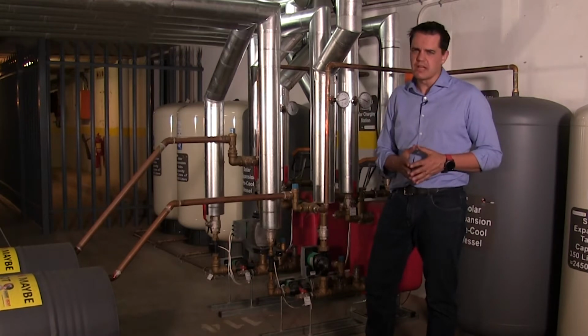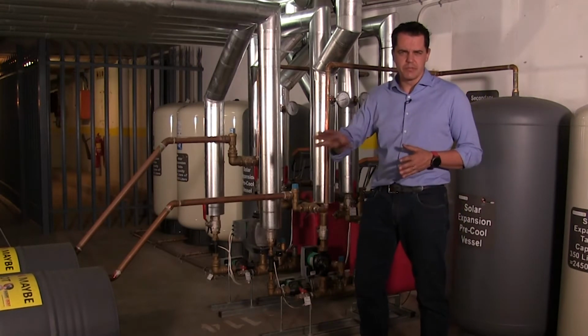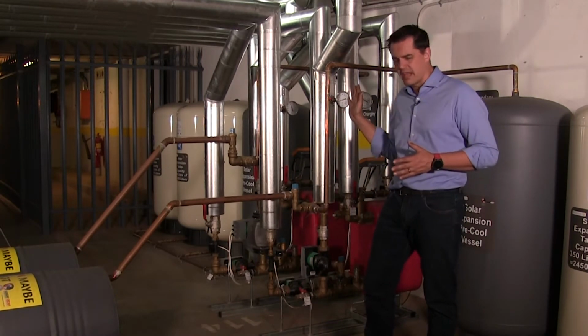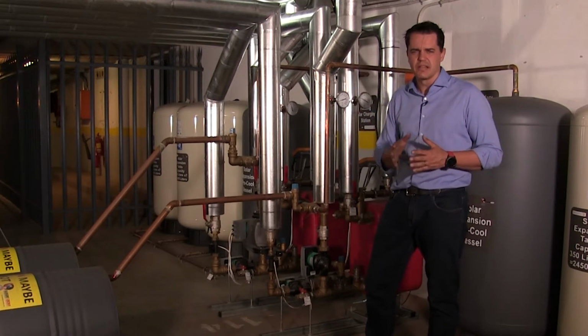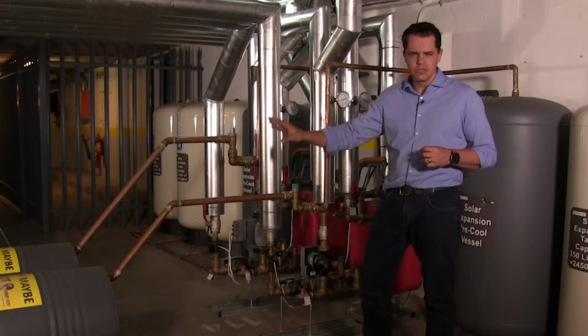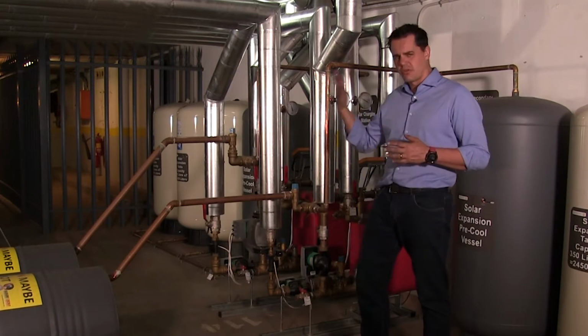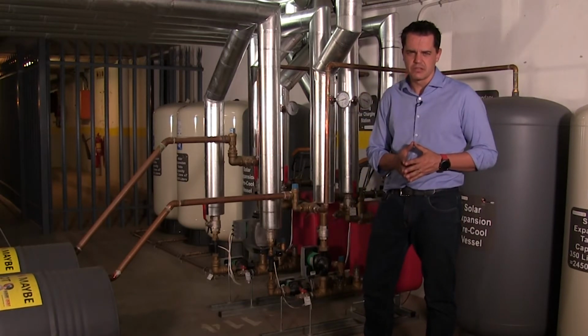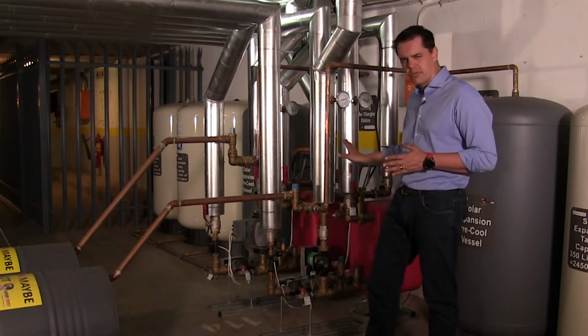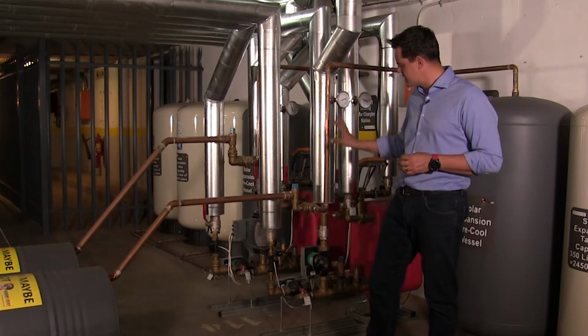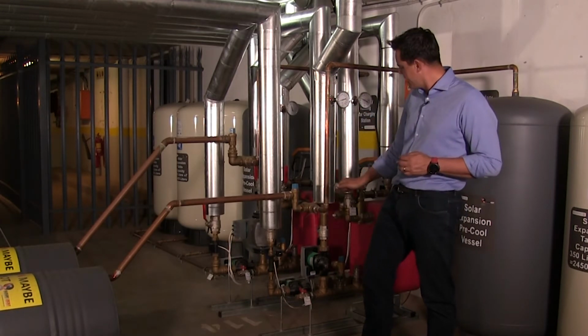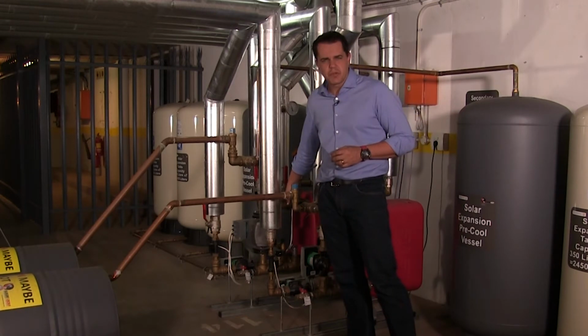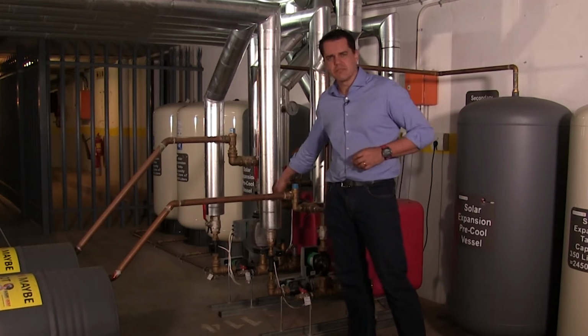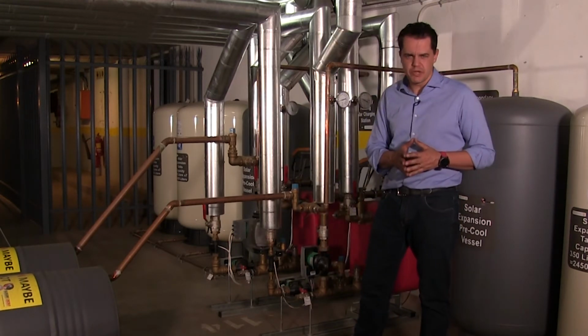Again, similar to the other plants, the reason for the drum is visually that you can identify that the system has released glycol, and secondly also that we can use that same glycol again to repressurize the system and to load the glycol. The other way that you can see that the system has released glycol is at the back here. We've got a pressure gauge. So the system runs at a 3-bar pressure.